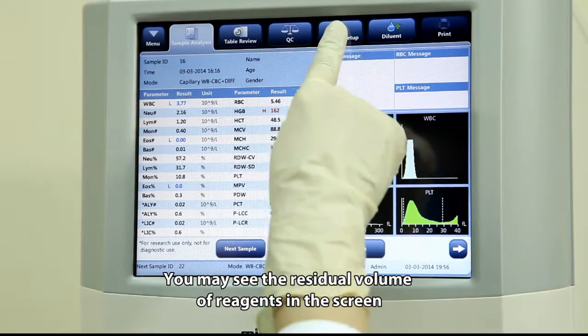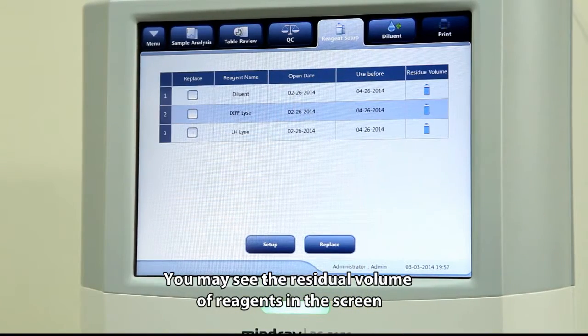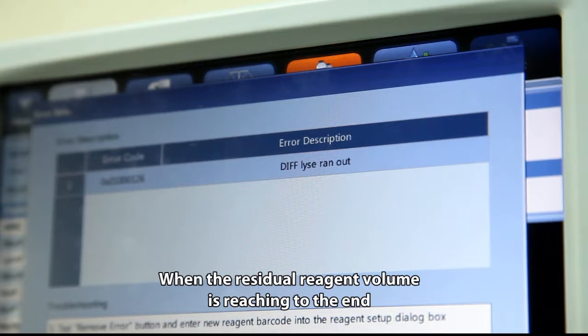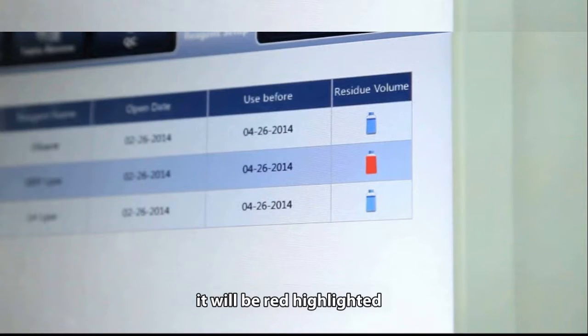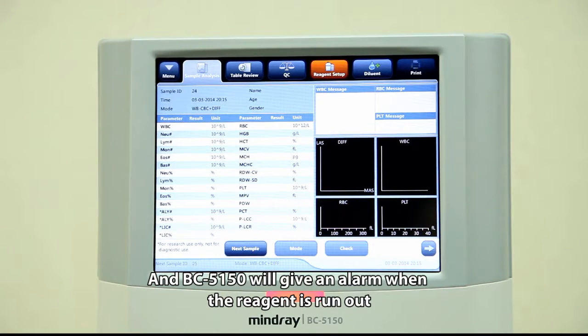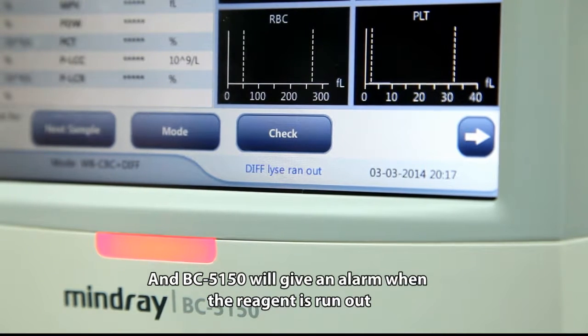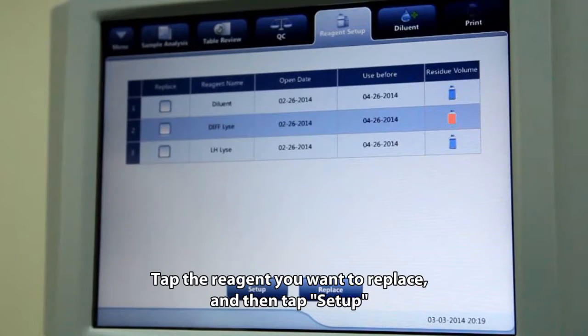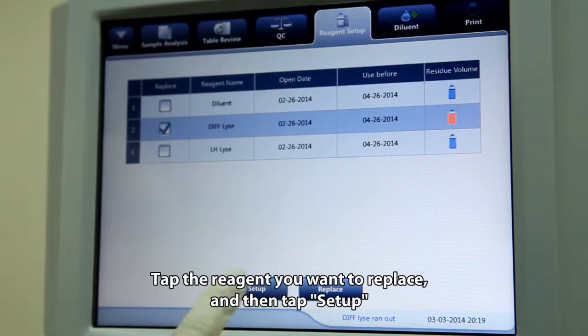You may see the residual volume of reagents on the screen. When the residual reagent volume is reaching the end, it will be highlighted in red, and BC5150 will give an alarm when the reagent has run out. Tap the reagent you want to replace and then tap Setup.